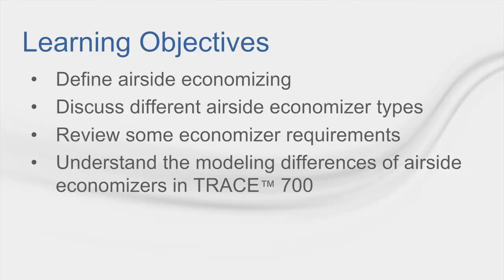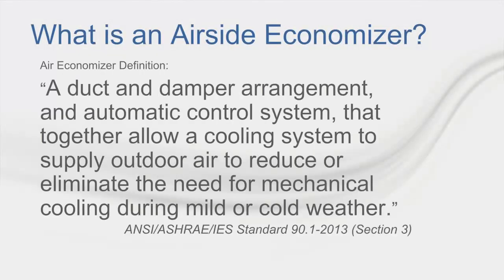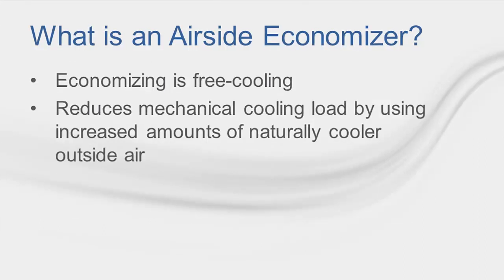Let's begin by discussing what an airside economizer is. According to ASHRAE Standard 90.1-2013, an air economizer is defined as a duct and damper arrangement and automatic control system that together allow a cooling system to supply outdoor air to reduce or eliminate the need for mechanical cooling during mild or cold weather. Essentially, airside economizers are a form of free cooling. By increasing the amount of outdoor air or ventilation air beyond mandated minimums, the load on a cooling plant can be decreased, saving energy and money in the process.